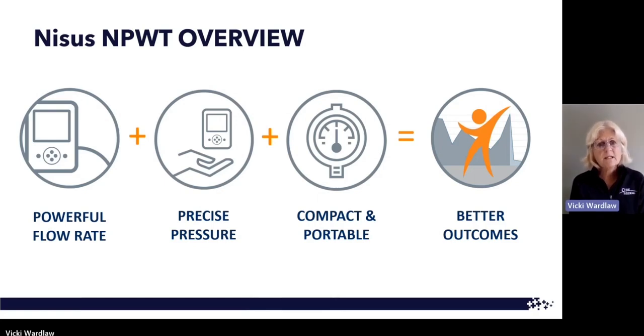Where this comes into play is those large, heavily exudating wounds, obviously, but also with our Drape, this pump can manage minor leaks. If you have a wrinkle or a bubble, or when your patient moves, you're getting a little bit of air pulling underneath the dressing itself. The device can handle that and keep to set pressure or your prescribed pressure without alarming automatically. So your end users, your nurses, and your patients will have fewer leak alarms.